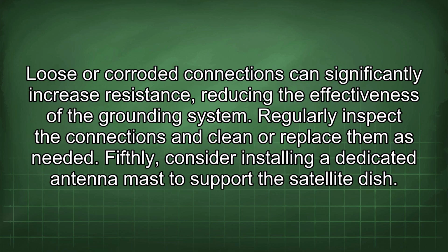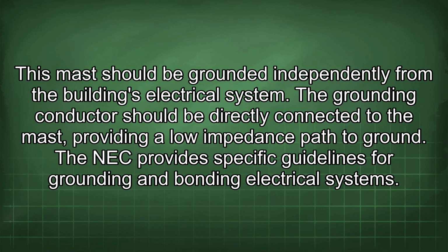Fifthly, consider installing a dedicated antenna mast to support the satellite dish. This mast should be grounded independently from the building's electrical system. The grounding conductor should be directly connected to the mast, providing a low impedance path to ground.